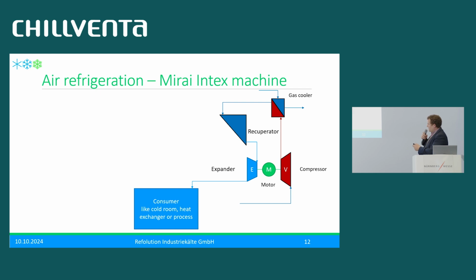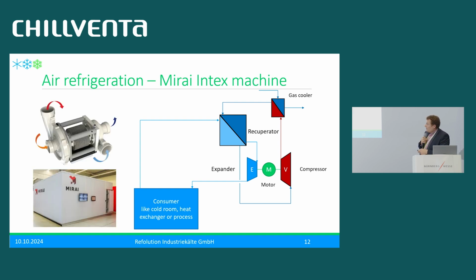We go into the recuperator that I promise you will understand in a second. We are here at -75. We expand from 1 bar overpressure to ambient pressure. We are at -100. The -80 room heats up our -100 air to -80. We suck back the -80 air. We go into the recuperator. We said we are at +20, -80, same mass flow, gives here +15, and we go back into recompression. One rotating equipment, simple cycle. But the beauty of this is the turbo expander. That's why it's now and not 30 years ago. This machine, the smallest, turns with 86,000 RPM, flying on an air bearing.